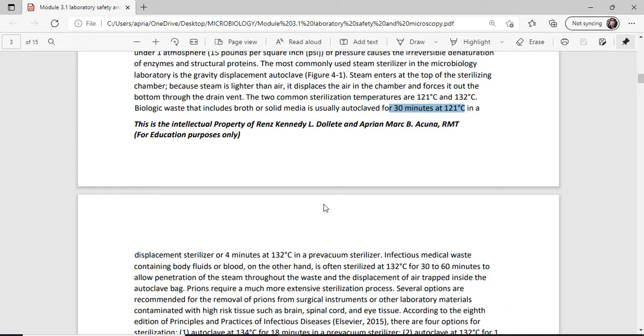That means it takes longer to wait for it to reach 132 degrees Celsius. Then for 4 minutes, that's already enough. After that 4 minutes, you still need to wait for the steam to settle down to cool it off a little bit. So even though it's only 4 minutes of sterilizing, you wait longer overall. But if it's just 121 degrees, it's quicker to reach that temperature, then you just proceed with sterilizing for the countdown time.